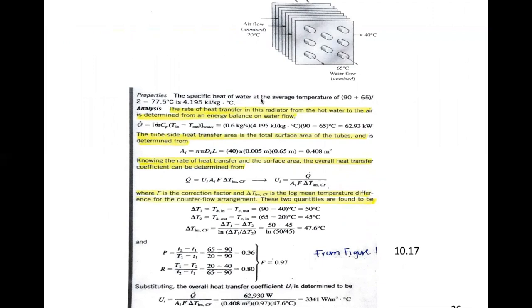We have the specific heat at the average temperature of 90°C inlet and 65°C outlet. At 77.5°C, Cp = 4.195 kJ/kg·°C. The rate of heat transfer from the hot water to the air is determined from an energy balance on the water flow, because we are given the mass flow rate of 0.6 kg/s and both temperatures. So ṁ·Cp·ΔT gives us 62.93 kilowatts.